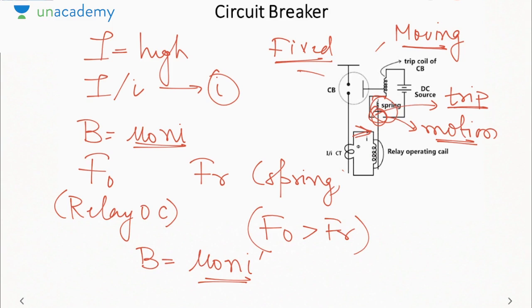Now the transformer that is used, the current transformer, this one, this is your protective current transformer. Why? Because this current transformer is used for protection. Now current transformers are also of two types. One that you will study in measurement is called an instrument transformer. Here it is called a protective transformer.